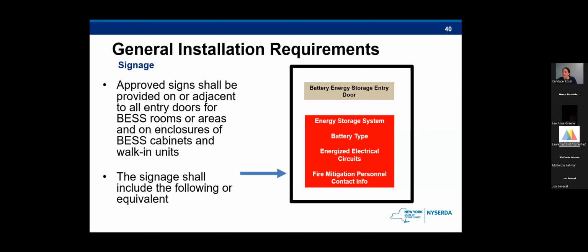And here we have the signage that's required for each battery energy storage system. It should be provided on all entry doors to storage system rooms, to walk-in units located outdoors, on rooftops or in open parking garages, and on the enclosure of cabinets. This is really necessary to let people know that there are batteries in this location, what type of batteries, that there is electrical, that it is energized, and what the emergency contact information is in case of an incident. There may be additional signs required from the electric code, but this is specifically what is required in the fire code. You definitely don't want random people walking into rooms with these systems in there. And if there is an incident, you want to be aware of what you're walking into.